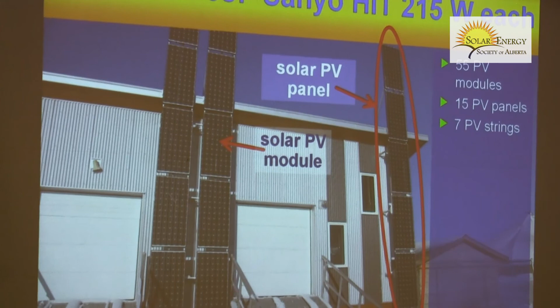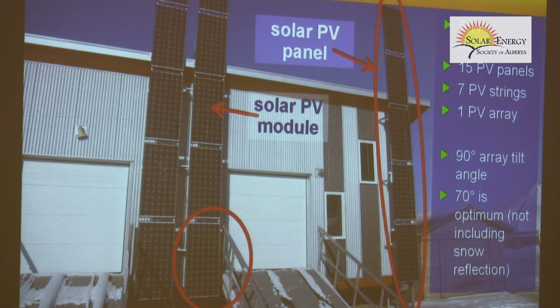What's fascinating also is that there's some shading, because the railing will shade the lower solar modules at certain times of day. I had to take that into consideration as I was setting up the strings, so I sacrificed one of the inverters and put as few modules as possible on that string so it would have the least interference from the railing. There were about 5 modules affected by this shading.